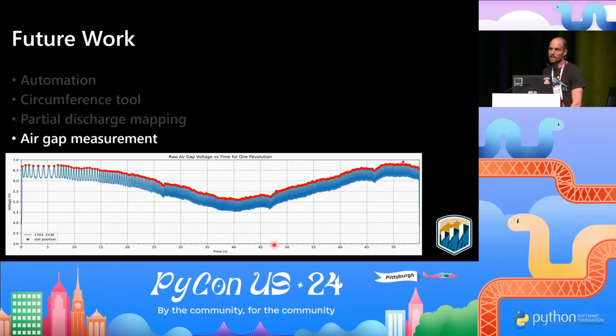Air gap measurement. So again, there's a spinning part and a stationary part, and between them is about an inch. If this changes, magnetic force changes with distance. So if the air gap is changing around the circumference of the machine, you get cyclic forcing. And if the cyclic forcing is big enough, you can rip the machine apart. We don't want that. So we often do tests to determine the shape of the machine. Is it circular? Is the air gap changing around the circumference?